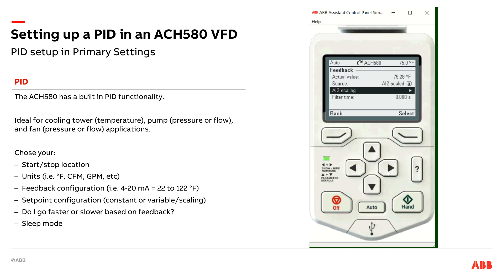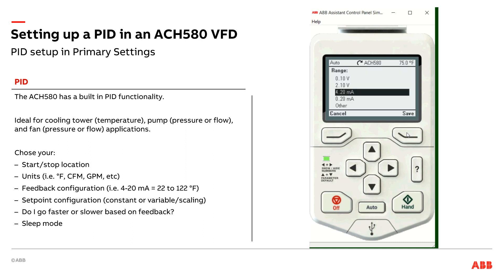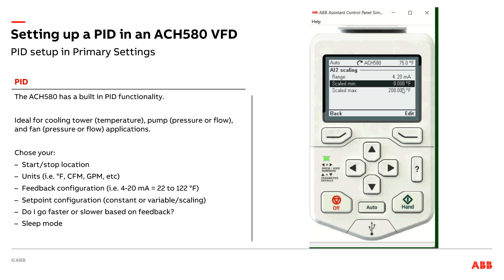The next thing I'm going to do is my scaling. Analog input 2 on the drive is where my sensor is landed. Now I set the range of that sensor — whether it's a 4 to 20 milliamp sensor, a 2 to 10 volt, or 0 to 10 volt. Let's assume it's a 4 to 20 milliamp sensor. You simply say when the sensor's at 4 milliamps, that's the equivalent of 0 degrees Fahrenheit in this example, or if it's 20 milliamps, it's 200 degrees Fahrenheit. Just find out what your sensor is and align the scaling to match it.